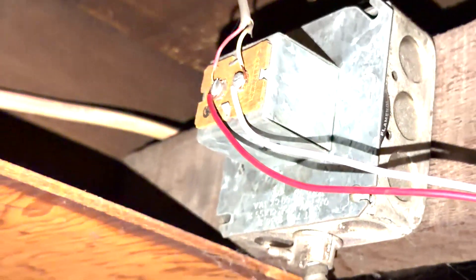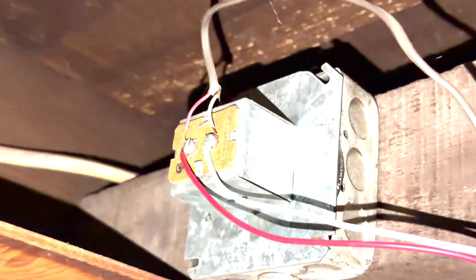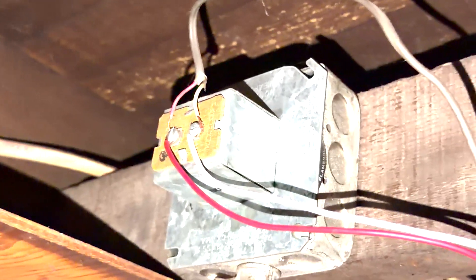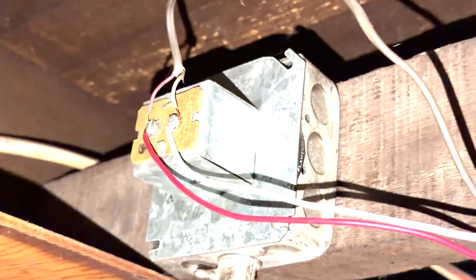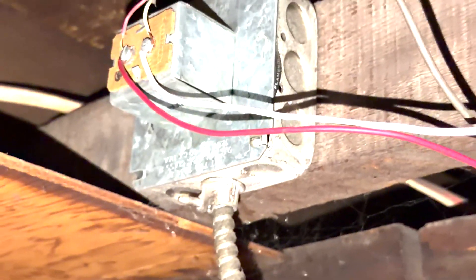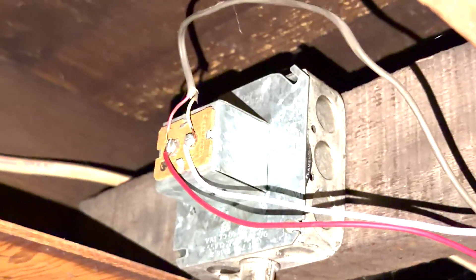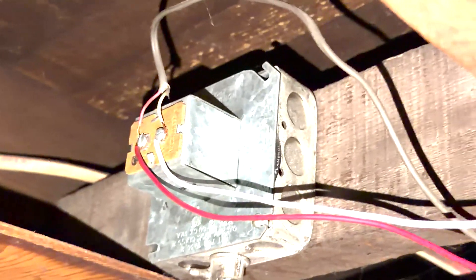But over here is another important piece. This is the 24-volt transformer I'm using to power the Ecobee separately. Because again, the Aquastat doesn't supply any power via a C-wire. There's no way to get that additional power hooked up, so you need an external transformer. But in order to use an external transformer, you have to use this zone relay.